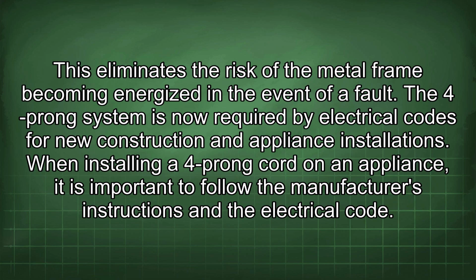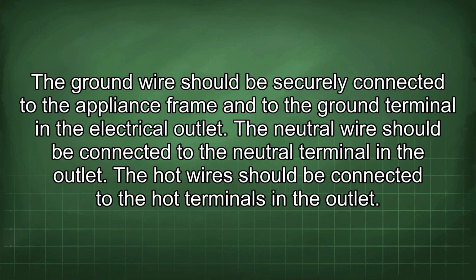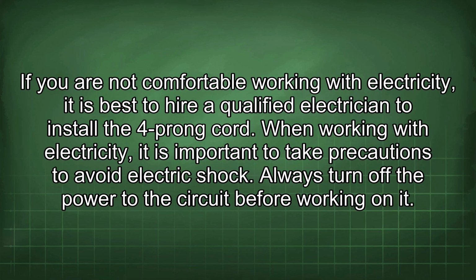When installing a 4-prong cord on an appliance, it is important to follow the manufacturer's instructions and the electrical code. The ground wire should be securely connected to the appliance frame and to the ground terminal in the electrical outlet. The neutral wire should be connected to the neutral terminal in the outlet. The hot wire should be connected to the hot terminals in the outlet. If you are not comfortable working with electricity, it is best to hire a qualified electrician to install the 4-prong cord. When working with electricity, it is important to take precautions to avoid electric shock.